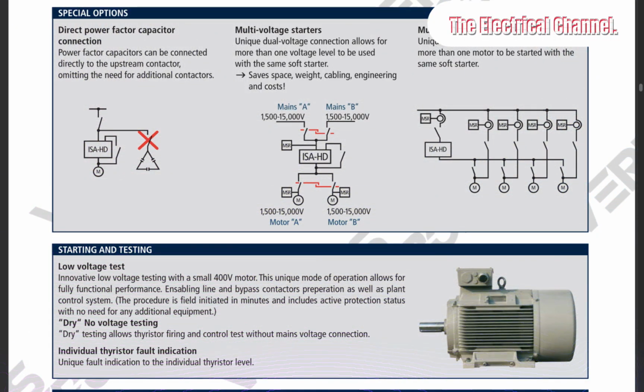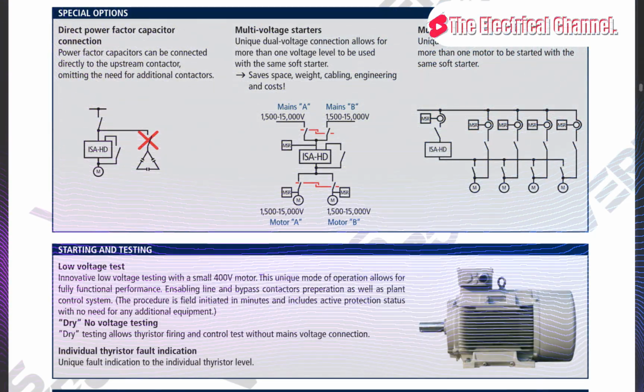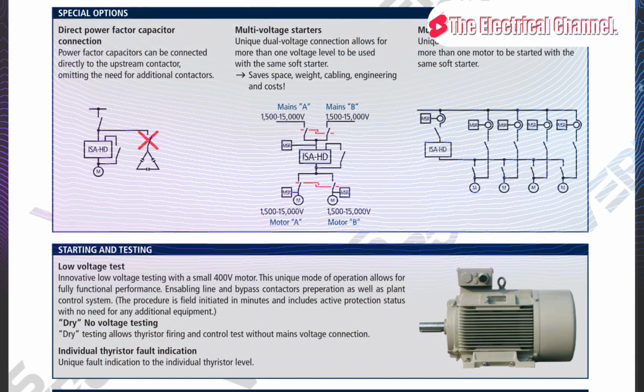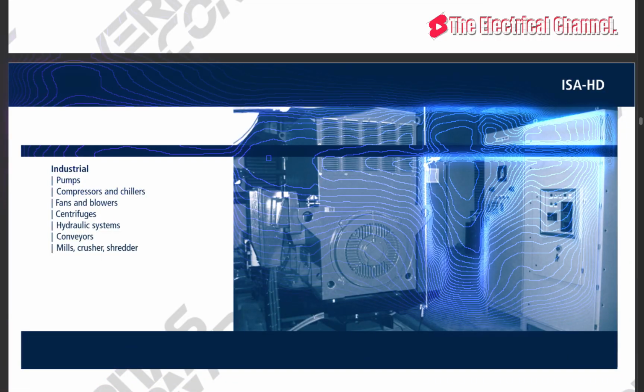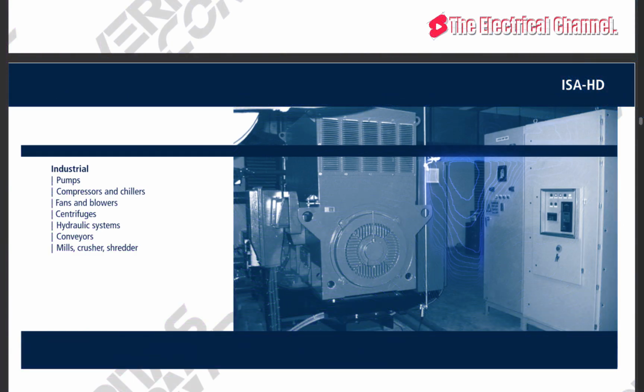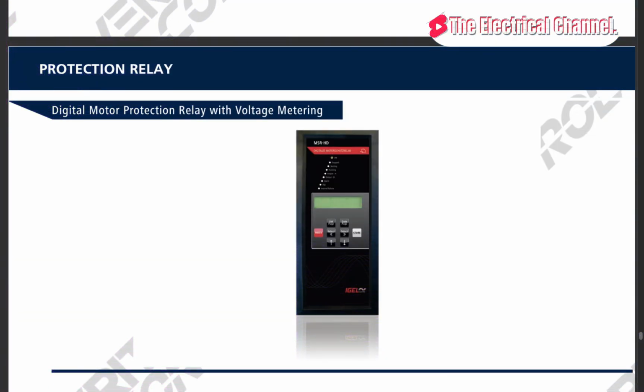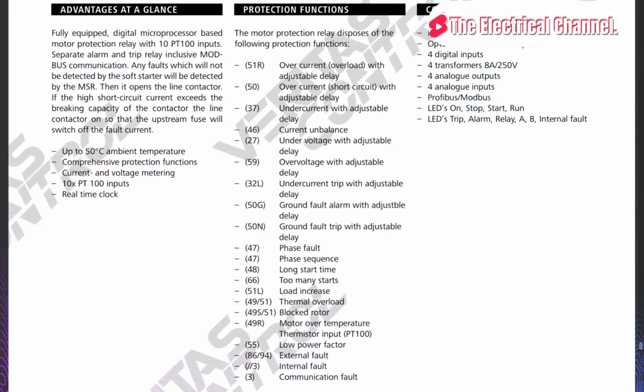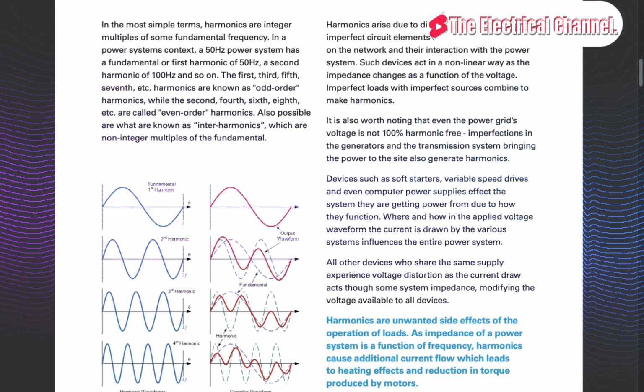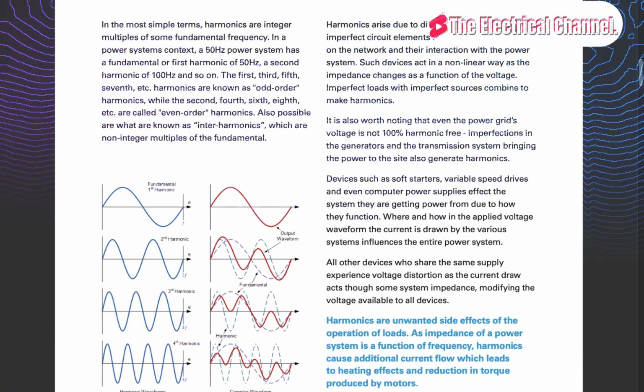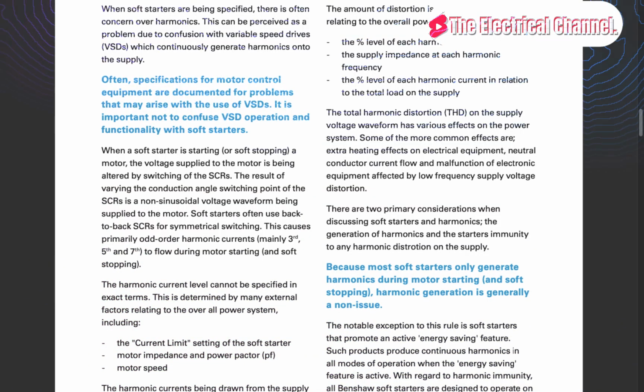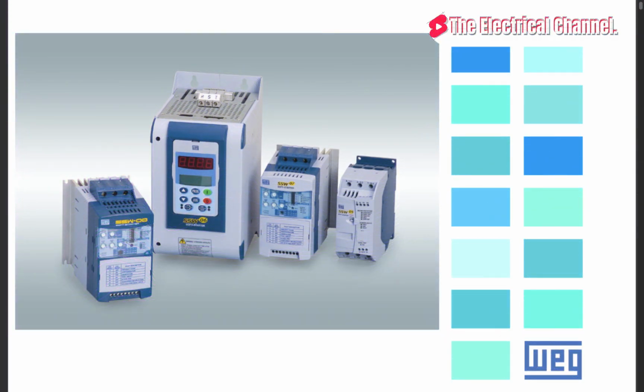Then, during the start, the firing signal is sent earlier and earlier, allowing a bigger and bigger part of the voltage to pass through the thyristors. Eventually, the firing signal is sent exactly after passing zero, allowing 100% of the voltage to pass through. By allowing more and more of the voltage to pass through the thyristors, this can be seen as ramping up the voltage from something called the initial voltage to the full voltage.